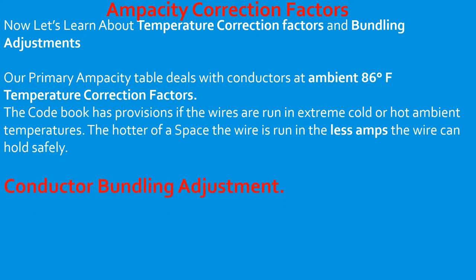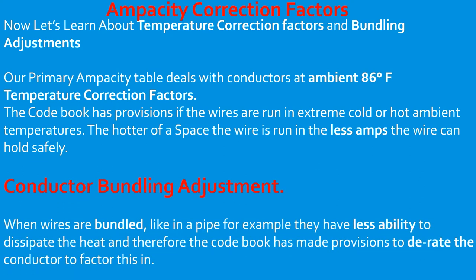Now let's look at conductor bundling adjustment. When wires are bundled — like in a pipe — they have less ability to dissipate that heat. Therefore, the codebook has made provisions to de-rate the conductors to factor this in. If we have a lot of wires jammed in a pipe, they're going to have less ability to dissipate the heat from the amperage, so they're allowed to handle fewer amps safely.